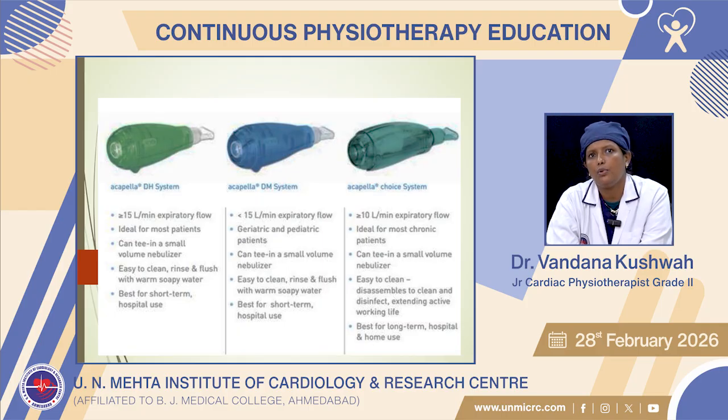And second is blue, for expiratory flow of less than 15 liters per minute, which geriatric and pediatric patients may use. It can be used with a small volume nebulizer, is easy to clean, rinsed and flushed with warm soapy water, and is best for short term hospital use.